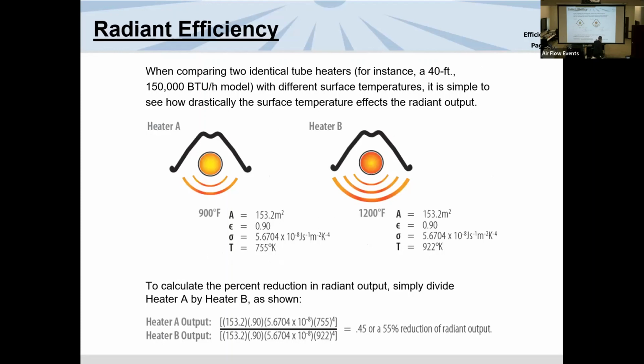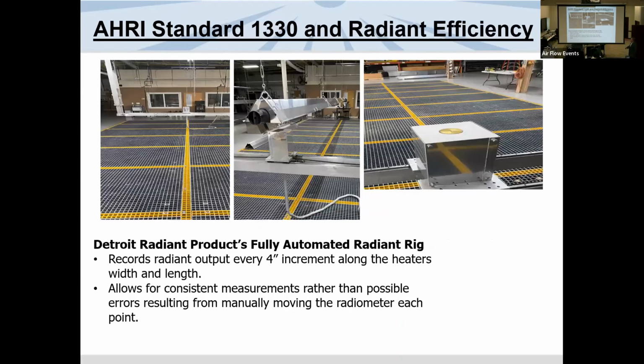This is the math demonstrating how we do the mathematical formula. But in reality, the next slide will show our rig. Okay, this little device right here sits on a whole rig, and it moves back and forth, and it's measuring how much radiant output is coming off the pipe and recording it, and it's giving us a visual depiction of any one of our heaters. This is what the infrared industry is going toward. They're infrared factors. Has anybody seen the infrared factor specs yet? So we score SEER numbers for air conditioners, right? It's a marketing number, right? It's all it is.